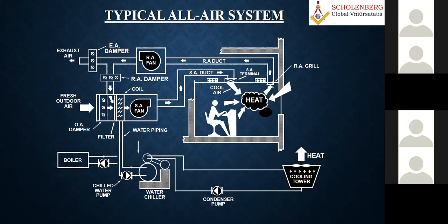This is what our standards define, which is what I've been talking about. For example, when designing a hospital's operation theaters, ASHRAE 170 says there should be no return air; everything should be completely exhausted. You don't take any return air. In operation theaters we also need air changes, about 25 to 30 air changes per hour, since it falls under class 100 or class 1000 in the clean room category. In that category, the distribution should also be laminar flow.